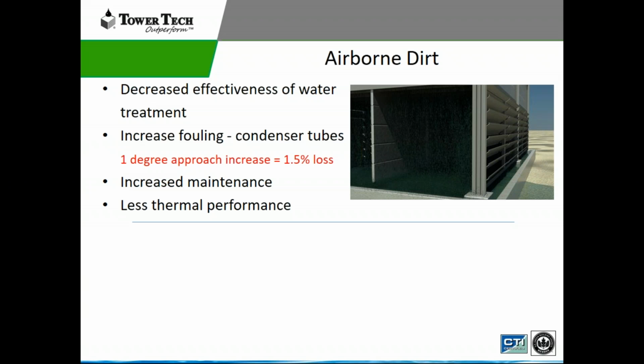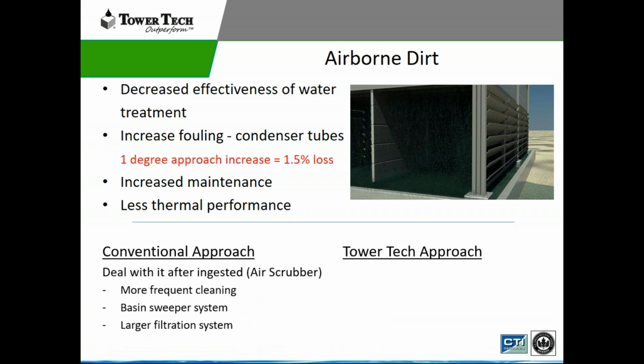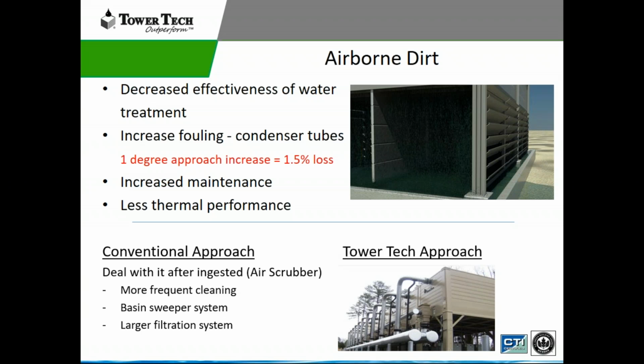Obviously, with the airborne dirt, we have increased maintenance and less thermal performance. From a conventional standpoint, what do you do? More frequent cleaning, basin sweeper systems, and larger filtration. The TowerTech approach, most of the time, is that we're on a 6-foot line. So that tower sits up 6 foot high. Air comes in through the bottom, so the dirt has a tougher pathway to get into the system versus a traditional system. So we typically have less dirt and debris. Our condenser tubes need less cleaning, so the chiller plant operates more efficiently. And in essence, we can have higher cycles of concentration, which is a big savings in water.